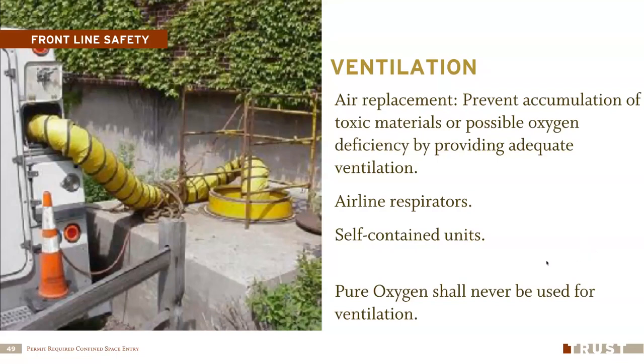One type is called dilution ventilation, where I dump a whole bunch of clean air in. The other is called local exhaust. So maybe I've got something bad releasing hazardous gases inside that space. I can put a duct right by that and ventilate it out so it doesn't fill the atmosphere where I'm going to be entering. If I'm doing local exhaust, I'm probably going to be doing dilution ventilation at the same time. And don't ever use pure oxygen for this, because that can cause you to blow up.